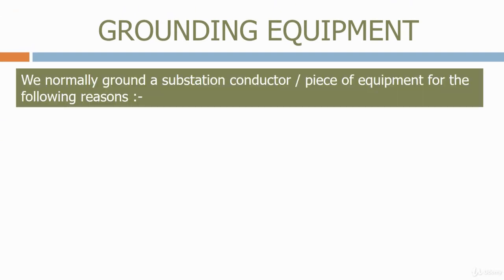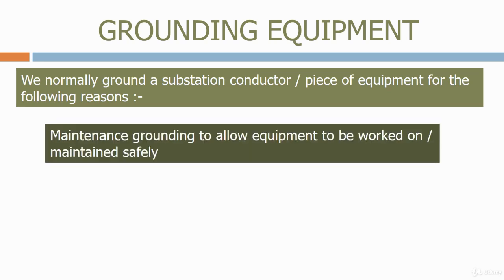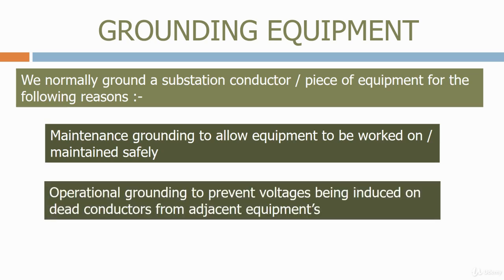We normally ground a substation conductor or piece of equipment for the following reasons. Maintenance grounding, to allow equipment to be worked on or maintained safely. Operational grounding, to prevent voltages being induced on dead conductors from adjacent equipment.